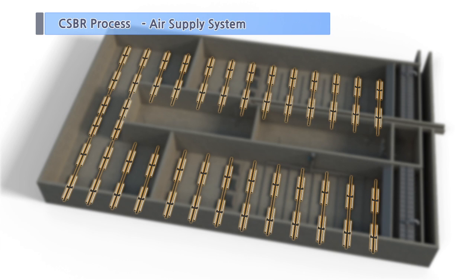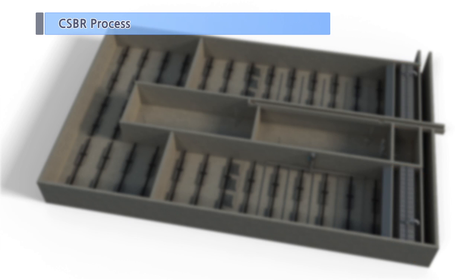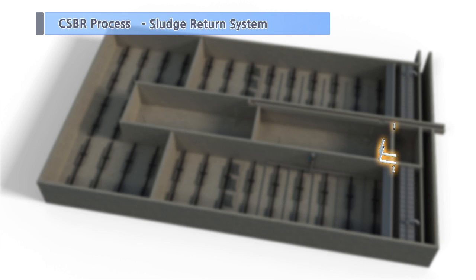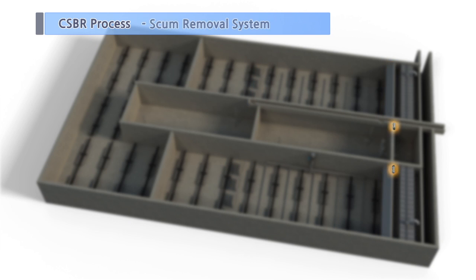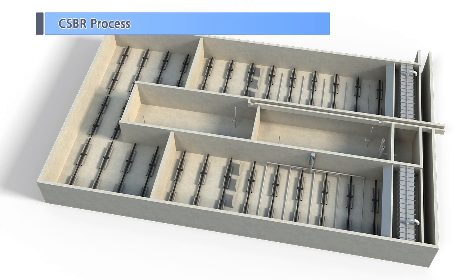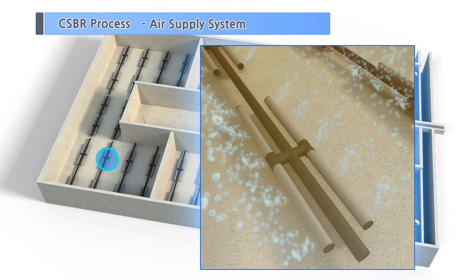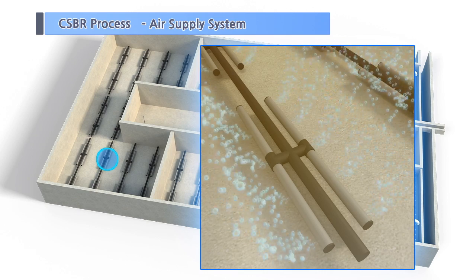The CSBR process consists of equipment including the air supply system, decanter, sludge wasting system, mixer, return, baffle, and scum removal system. The air supply system feeds air through diffusers, which are installed at the bottom of the cell, to remove organic matter, nitrogen, and phosphorus.